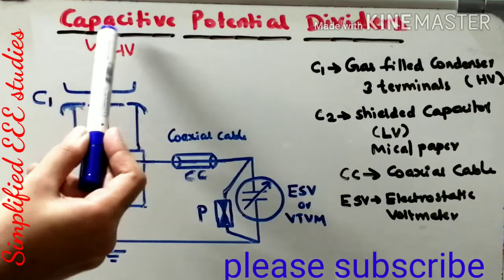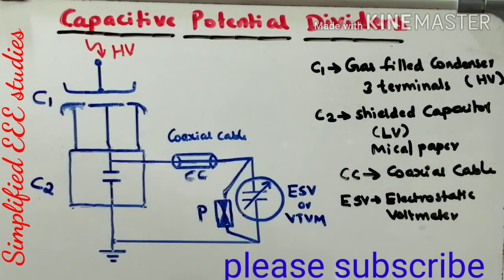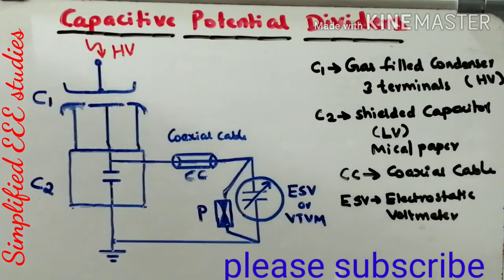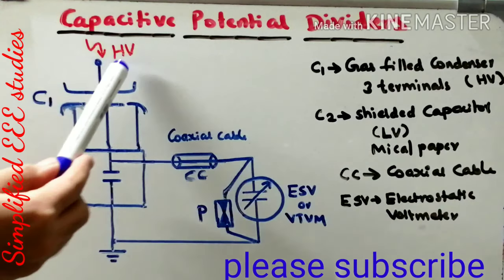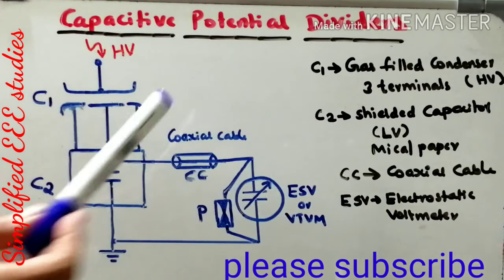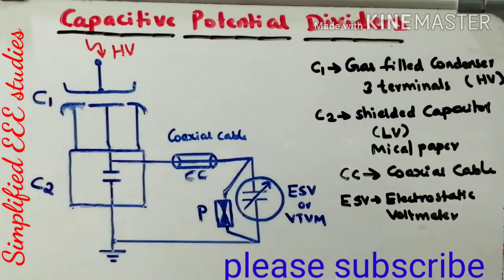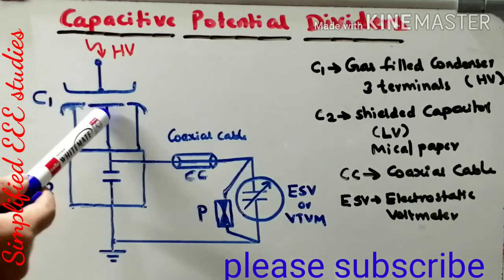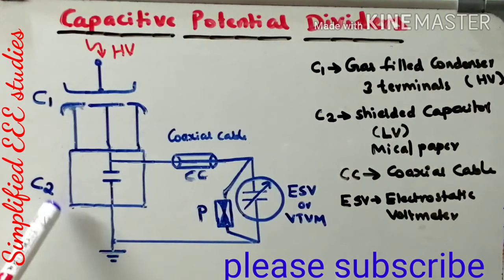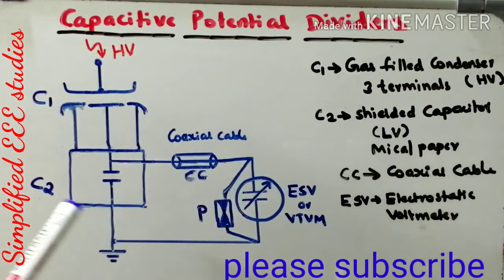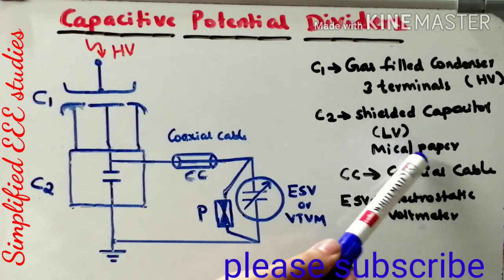Let us consider the circuit diagram of Capacitive Potential Divider. Our ultimate goal is to measure the high voltage which you operate externally. The overall high voltage is divided with the help of Capacitors C1 and C2. Here, C1 is known as Gas-Filled Condenser or Gas-Filled Capacitor. It comprises of three terminals and is also known as High-Voltage Capacitor. Similarly, C2 is known as Shielded Capacitor. To avoid stray loss, we provide a suitable shield.